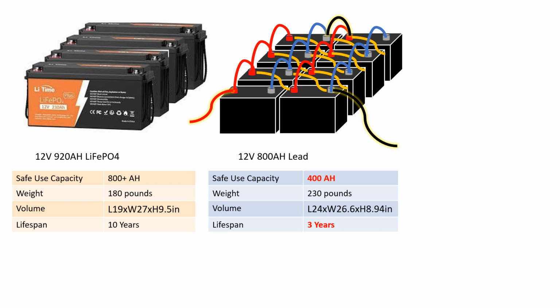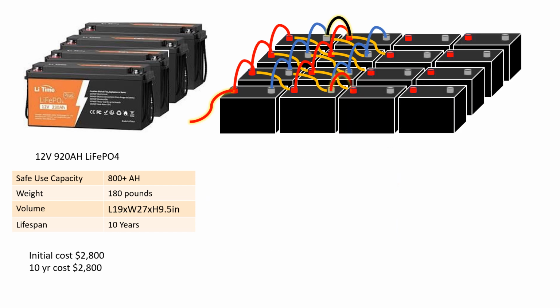That means in that 10-year time span, we're going to have to replace those batteries twice. So our initial cost with lithium is about $3,000, and our 10-year cost is the same. Our initial cost with the lead acid batteries is right around $1,700, with a 10-year cost of over $5,000. So we're now up to almost twice what the lithium cost, but we still only have 400 amp hours safe use capacity. So in order to get that safe use capacity up to the 800, we really need to double the size of that bank.